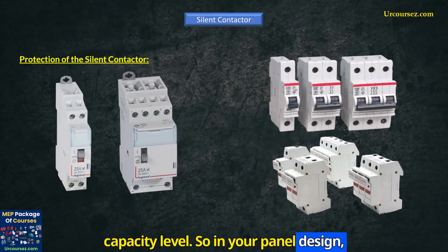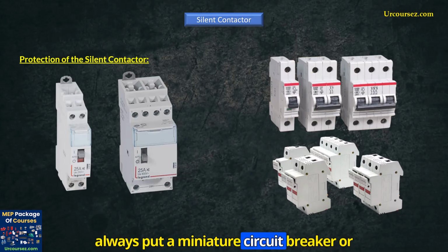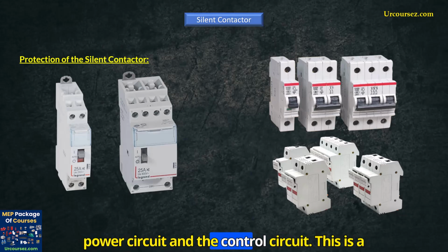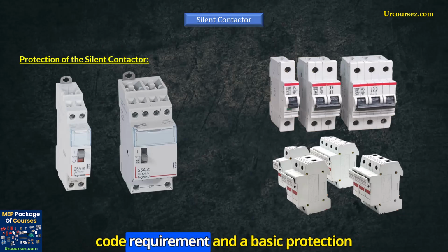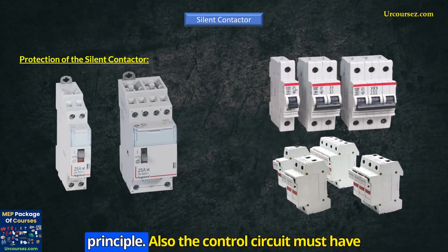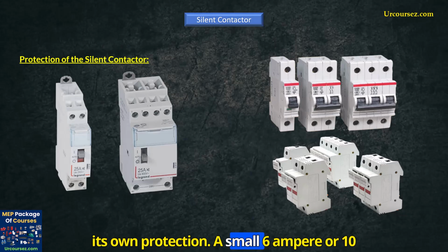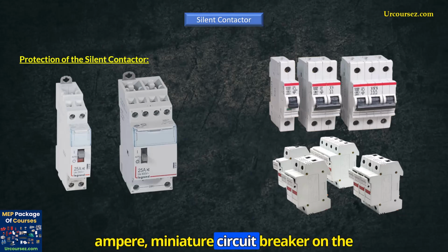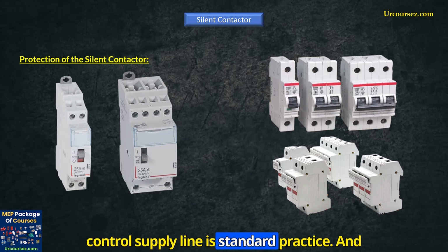So, in your panel design, always put a miniature circuit breaker or fuse upstream of the contactor on both the power circuit and the control circuit. This is a code requirement and a basic protection principle. Also, the control circuit must have its own protection. A small 6 amperes or 10 amperes miniature circuit breaker on the control supply line is standard practice.